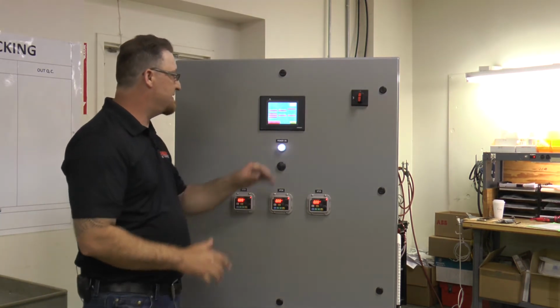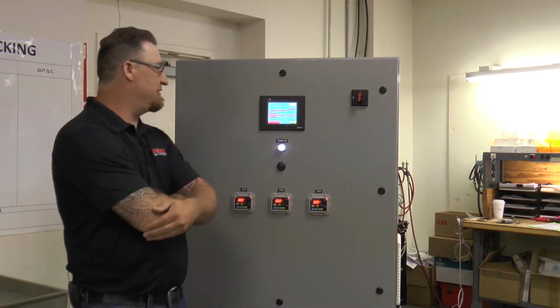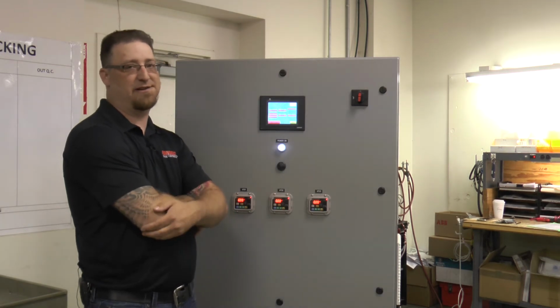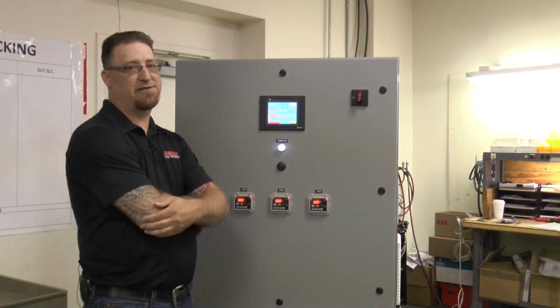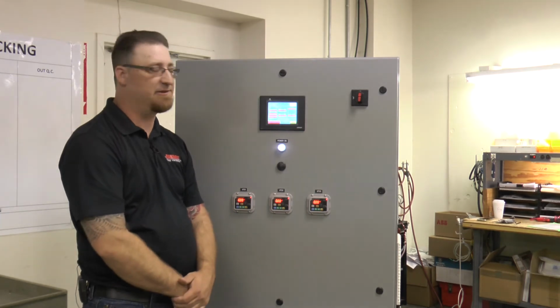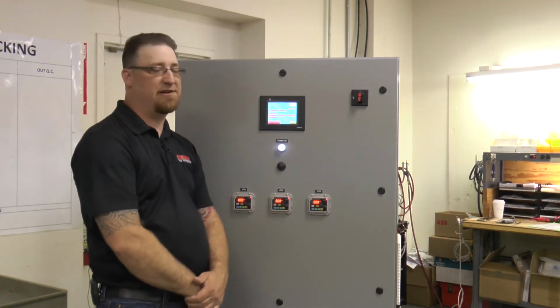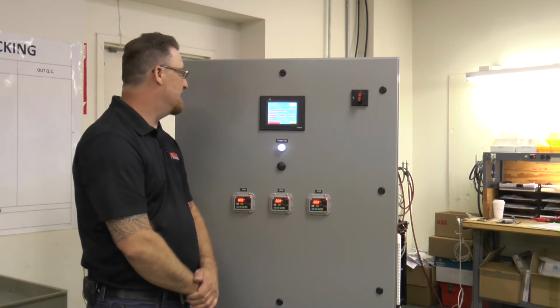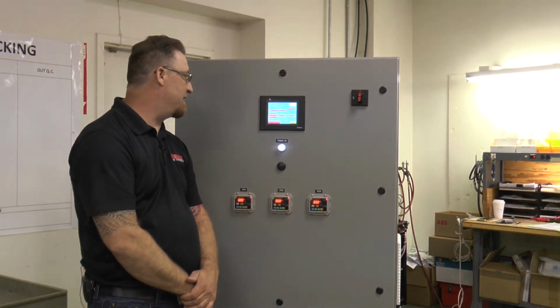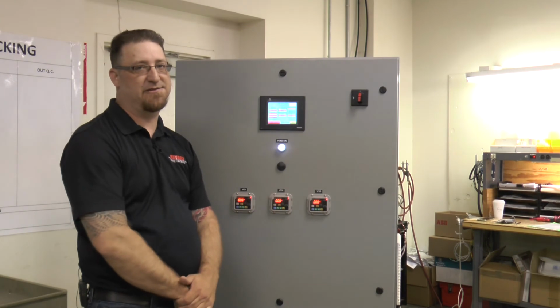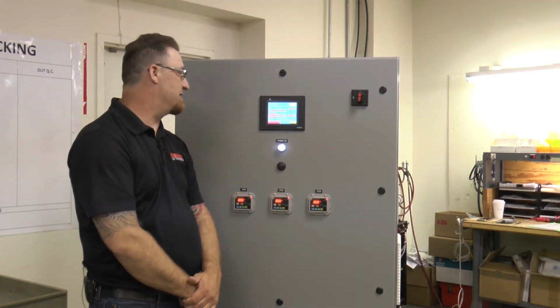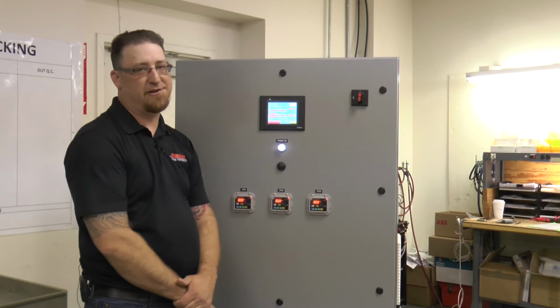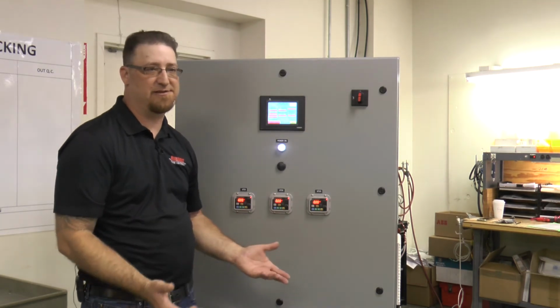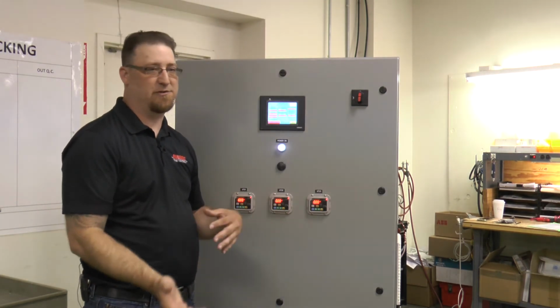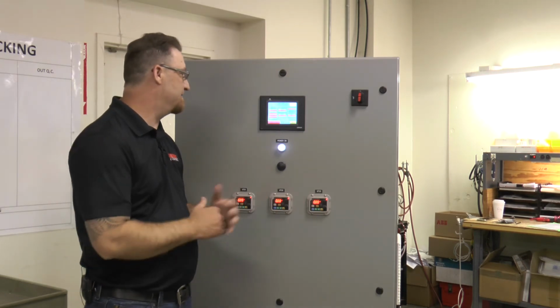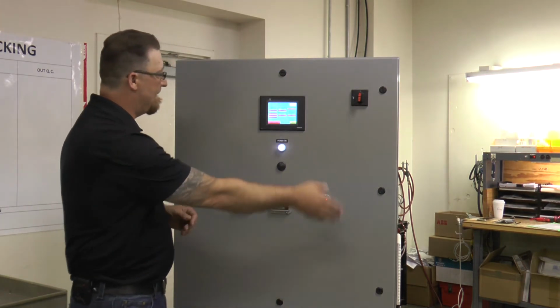So for this instance, on discharge, we have 0 to 250 psi or 0 to 500. We will include which transducer that you specified when ordering. So if you have a 0 to 500, we'll select that one. And then on suction, we have 4 different flavors. We have 0 to 25 on your suction, 0 to 250 transducer, or if you're using a tank, if you have a float switch, is it normally open or normally closed float switch, you can make those selections there. Moving on.